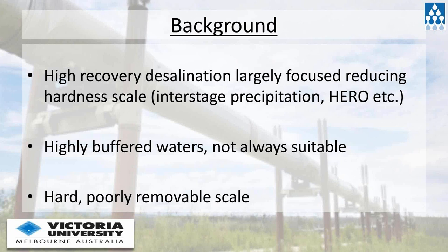Importantly, the silica that does tend to form is a very poorly removable scale. We saw earlier from Marlene's work that generally they don't recommend any chemicals necessarily for the removal of silica. It's not entirely true. There are some chemicals that we can try and get away with, but they're particularly nasty. Things like hydrofluoric acid and ammonium bifluoride that a lot of companies are very uncomfortable working with.